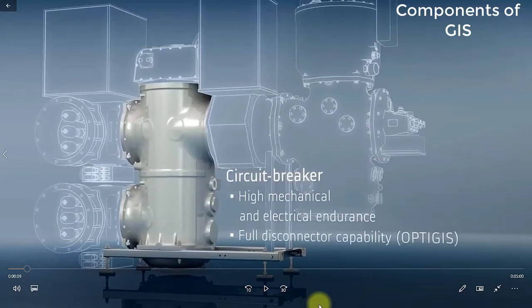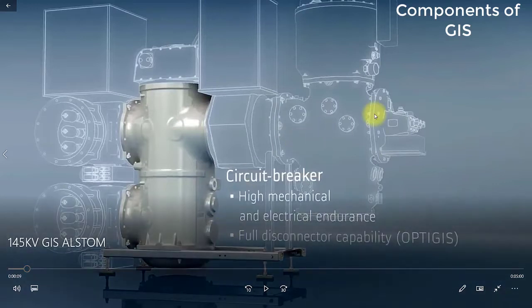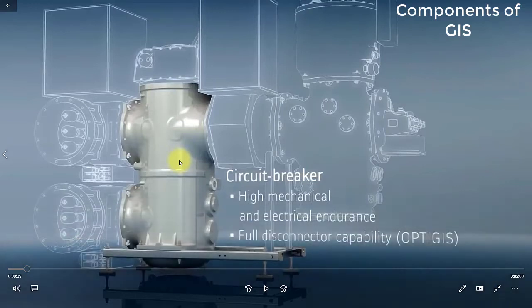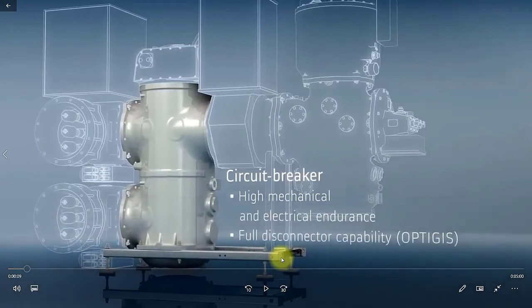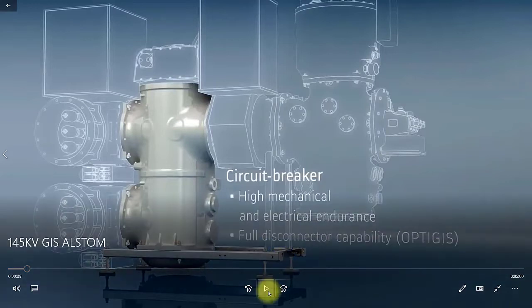Welcome friends. In this section we will go through the 3D animation of the gas insulated switchgear and see its different components. Here in the background you can see a 145 kV gas insulated switchgear by Alstom. This is the circuit breaker compartment — inside it are the circuit breaker fixed and moving contacts. This is a very important component for controlling switching on/off and current interruption. The gas pressure in the circuit breaker compartment is usually higher than other compartments because of the arc quenching process.